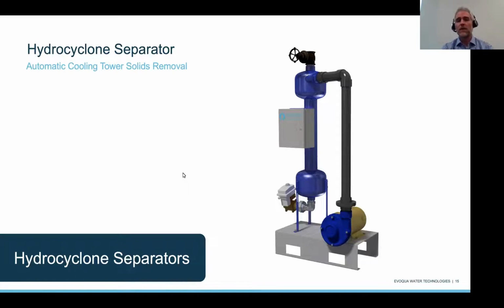Let's start with the hydrocyclone separator. Gary mentioned earlier, hydrocyclone separators are definitely a portion of the mitigation techniques of filtration. But remember, hydrocyclone separators are not filters. They are ultimately separators. But this technology is really the workhorse of the cooling industry, providing a robust solids protection for various different customers. But let's look deeper in what this technology can really do. When you look at centrifugal separators on a capability of micron performance and compare that to various different particulates you might find in a cooling environment, it's actually very interesting to see what the technology can do.